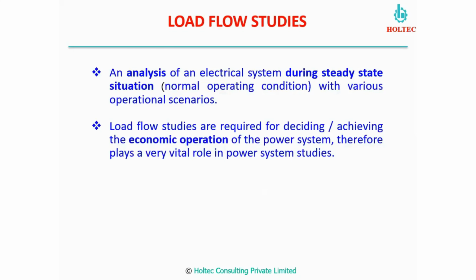The next is the load flow study. What is a load flow study? It is basically a study done during steady state or normal operating conditions with various operational scenarios. Same as we have done for the short circuit study, here also it will be done for normal operation for different operational scenarios. In load flow studies, the aim is to achieve the economical operation of the power system, where the efficiencies and the losses can be optimized and voltage levels will be optimized. This is basically the objective of the load flow studies.